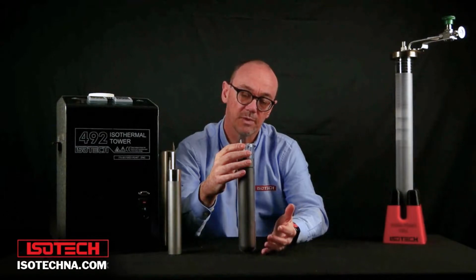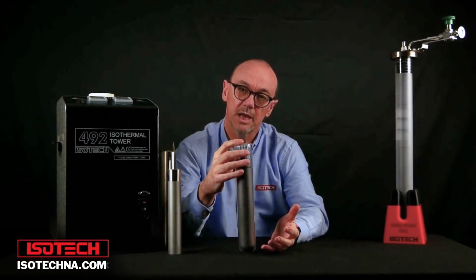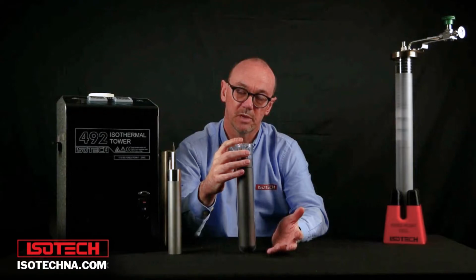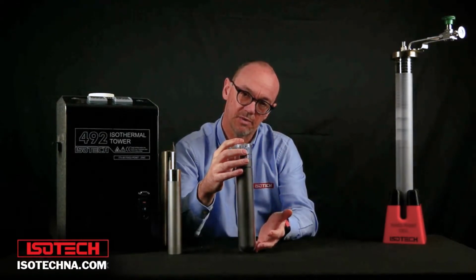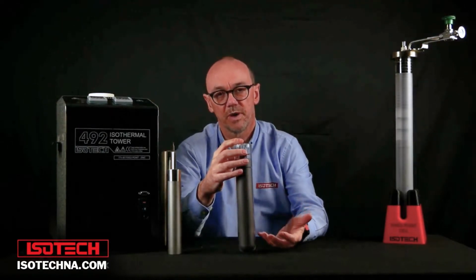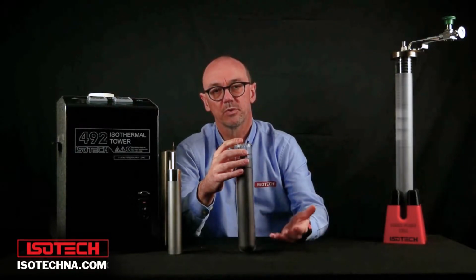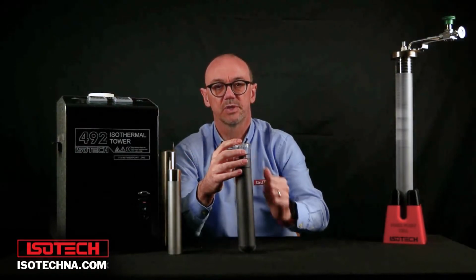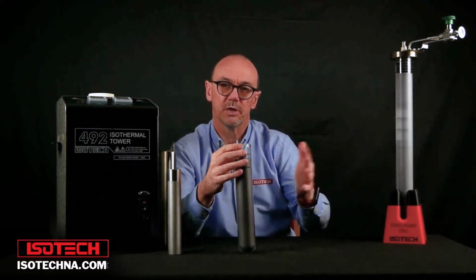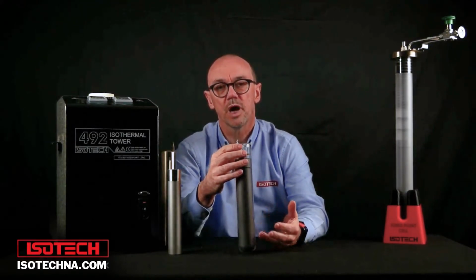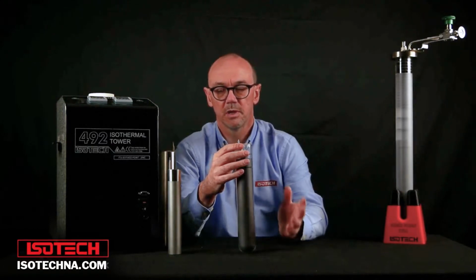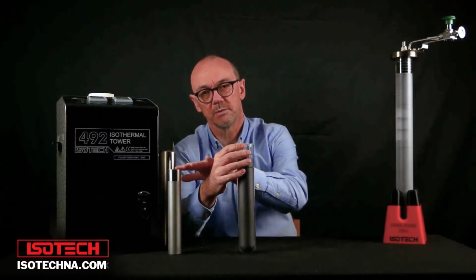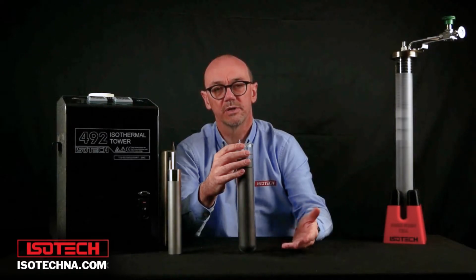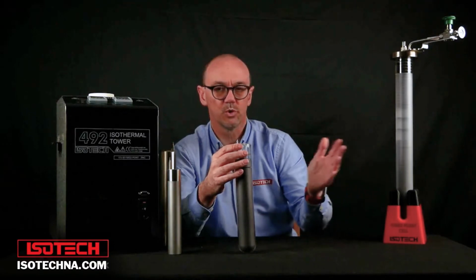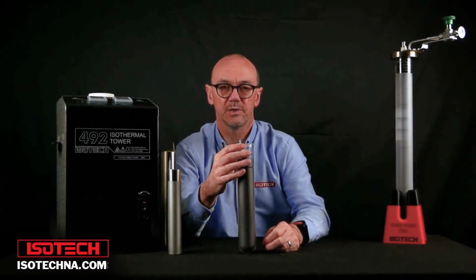So here we have a quartz glass aluminium fixed point cell. We can see through the glass the graphite crucible. Inside the graphite is the pure aluminium, and we can melt and freeze this in a furnace the same as the other cells. These optimal cells we would use really with primary SPRTs. The smaller, more affordable slim cells are good for working standards or very high accuracy industrial thermometers, whereas these would normally be used with primary SPRTs.